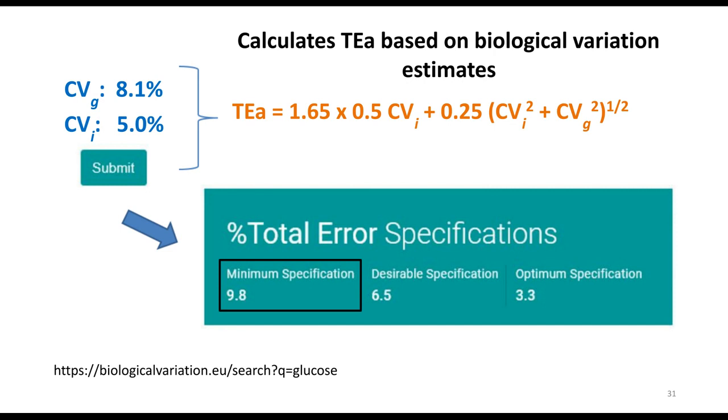And so that allowable error is 12.5% for glucose values that are greater than or equal to 100 milligrams per deciliter. So the lab director should make the final decision regarding the allowable total analytical error limits selected for a particular analyte.